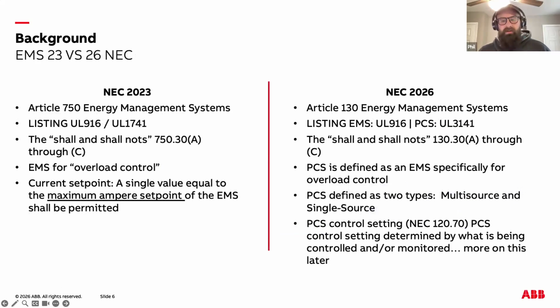So just to get started with some background, in the 23 cycle, the NEC placed EMS and PCS together under Article 750, and the definitions were vague enough that a lot of folks interpreted EMS as being capable of performing overload control functions. In fact, the phrase "EMS for overload control" appeared in several sections, which created confusion about whether EMS could be used for load calculations, conductor sizing, or service upgrade avoidance. To clarify, any use case, whether that be for convenience, cost savings, or overload control, was defined under the 23 code as EMS. In 2026, the code does a great job of clarifying what EMS and what PCS can be employed for separately.